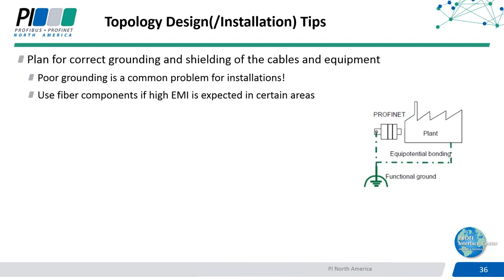EMI can come in from a lot of different sources nowadays, such as lighting, your HVAC system, and even other ways. So everyone, please write a note to yourself. If an issue like this occurs, it can be darned expensive and really hard to isolate in a poorly designed system. I mean, red lights will start flashing, but nobody knows what's causing the red light anymore, because it's a lower level issue, and those noise issues are really hard to track down. So please, to help with that, we have a functional earthing and shielding guide where you can get more details about this that I would highly recommend.